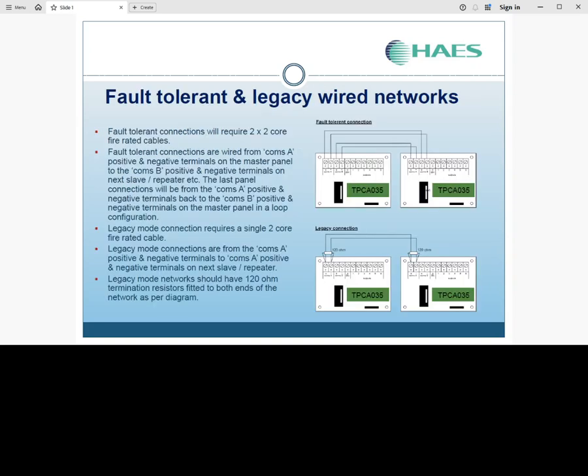Fault-tolerant and legacy wired networks. Fault-tolerant connections will require 2 times 2 core fire-rated cables. Fault-tolerant connections are wired from COMS A positive and negative terminals on the master panel to the COMS B positive and negative terminals on the next slave or repeater. The last panel connections will be from the COMS A positive and negative back to the COMS B positive and negative terminals on the master panel in a loop configuration. This can be seen to the right hand side.